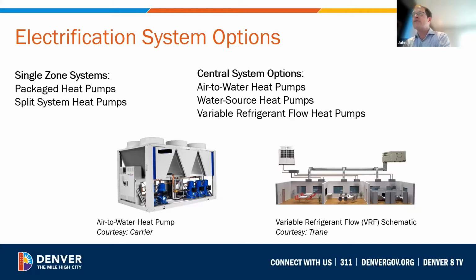Electric heating systems are often paired with dedicated outside air systems to provide ventilation. And as I mentioned, they can cycle the systems on and off with the load and have the DOAS system being the only system running continuously to serve the ventilation need. This will serve to reduce the fan energy for improved energy performance. So these are just some of the options available. There's certainly a number of options available beyond these listed.